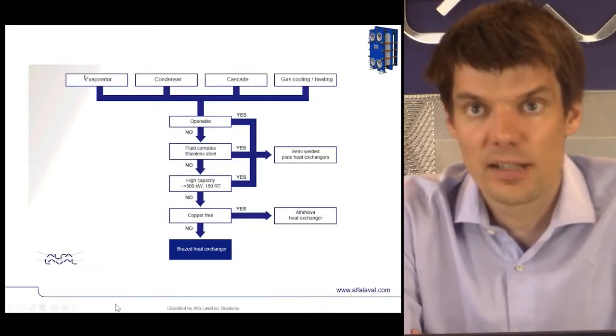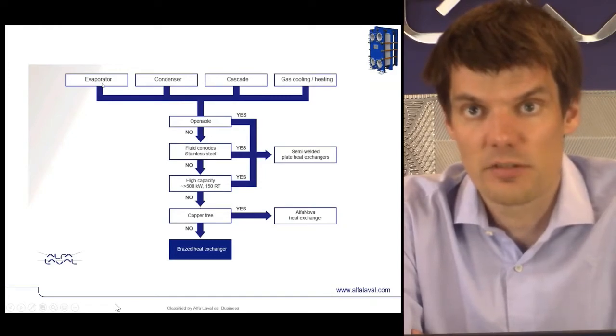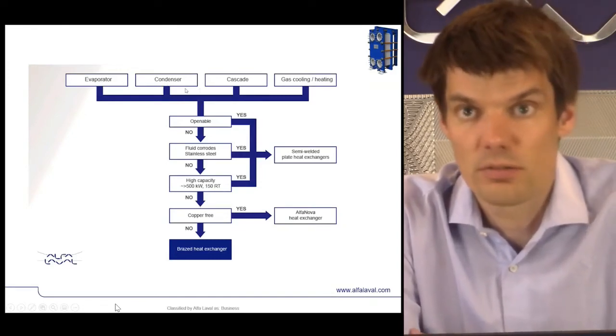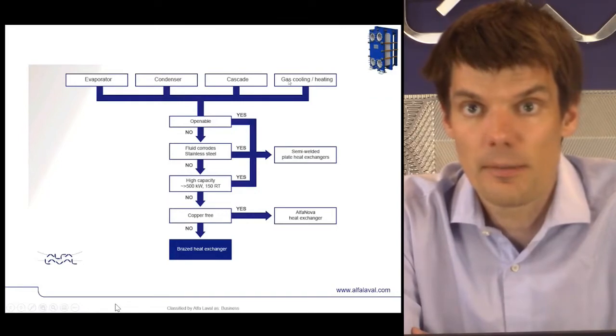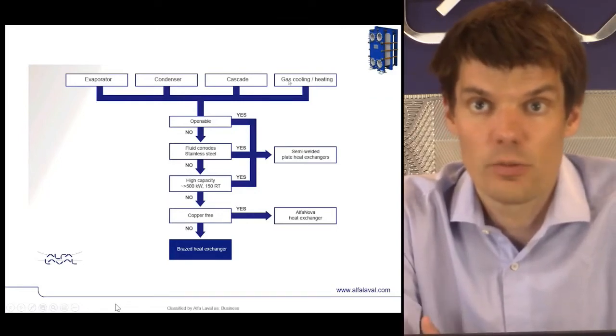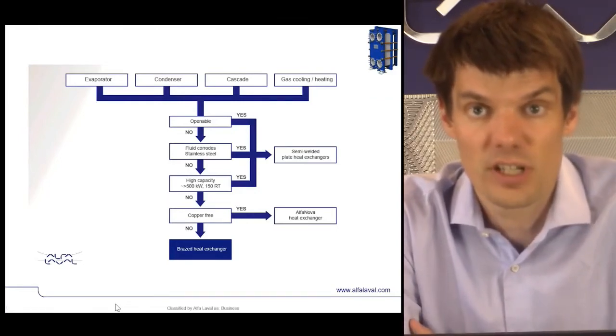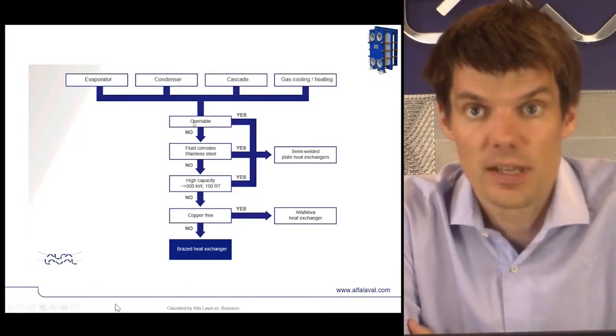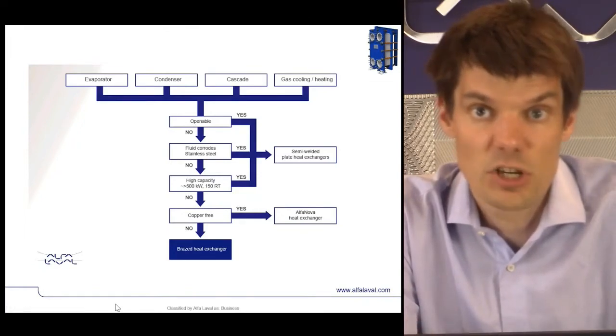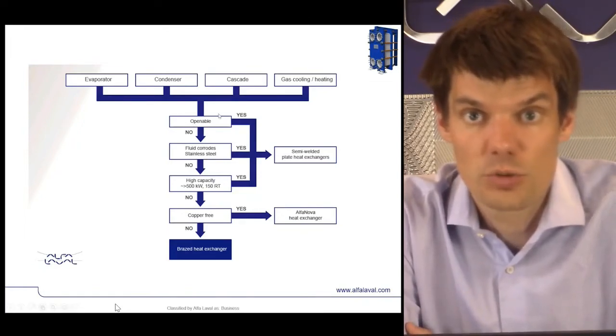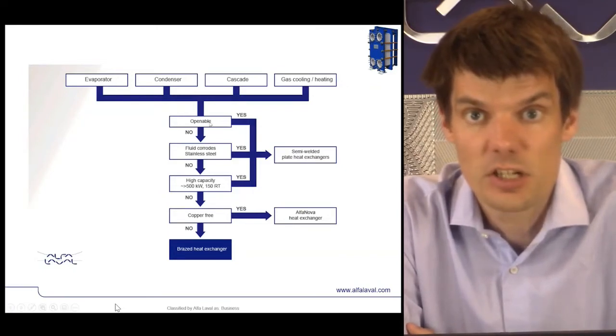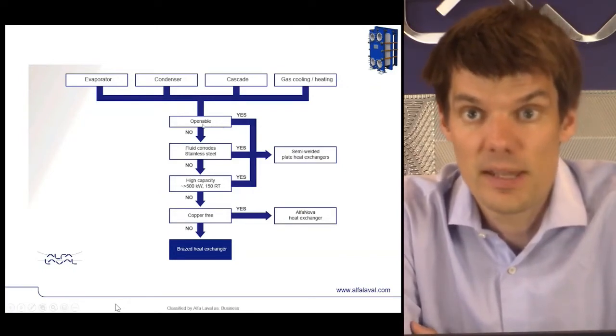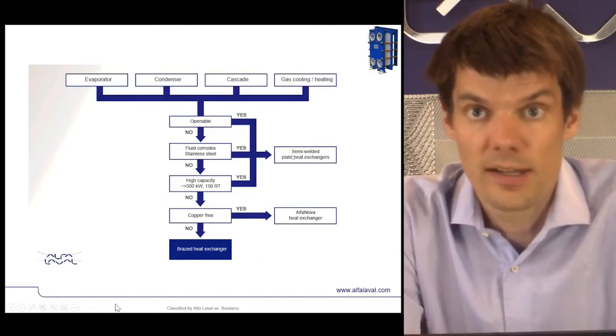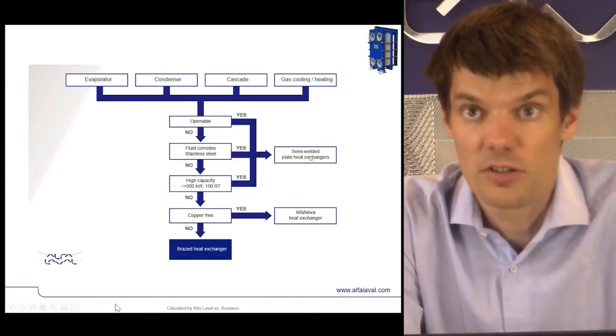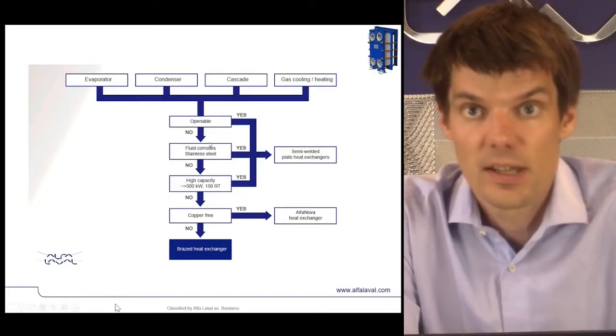If we had identified a need for a plate heat exchanger, for instance, as an evaporator, condenser, or oil cooler, one has to ask themselves what requirements are to put on this application. If the application is, for instance, dirty water or dirty brine, which require frequent cleaning of the heat exchanger, it should preferably be an openable one, and then the semi-welded plate heat exchanger is the best choice.